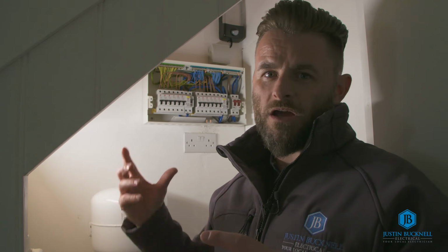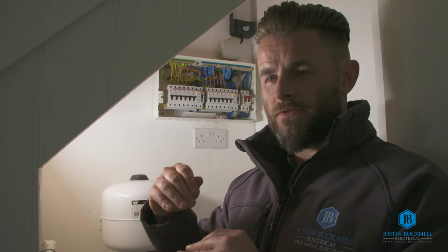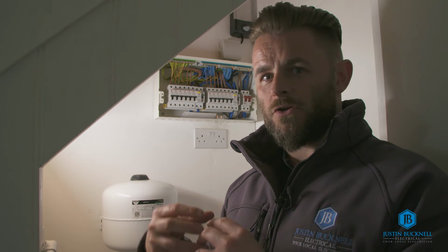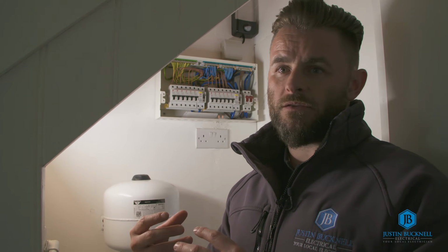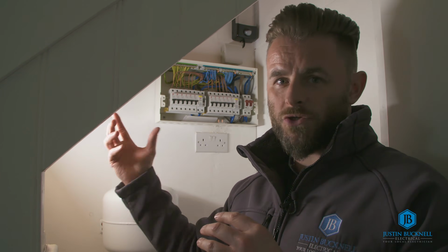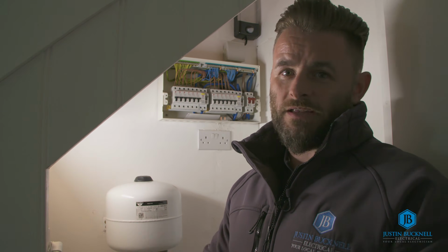The purpose of an SWA cable being glanded each end and earthed is that in the event of any damage that then results in the outer strands making contact with one of the live conductors within the cable, it will cause the covering MCB to trip, and that will obviously provide disconnection and cut off the circuit from any potential harm. The issue with this SWA cable not being earthed at either end is that the outer strands are not making connection to the earthing system at all.